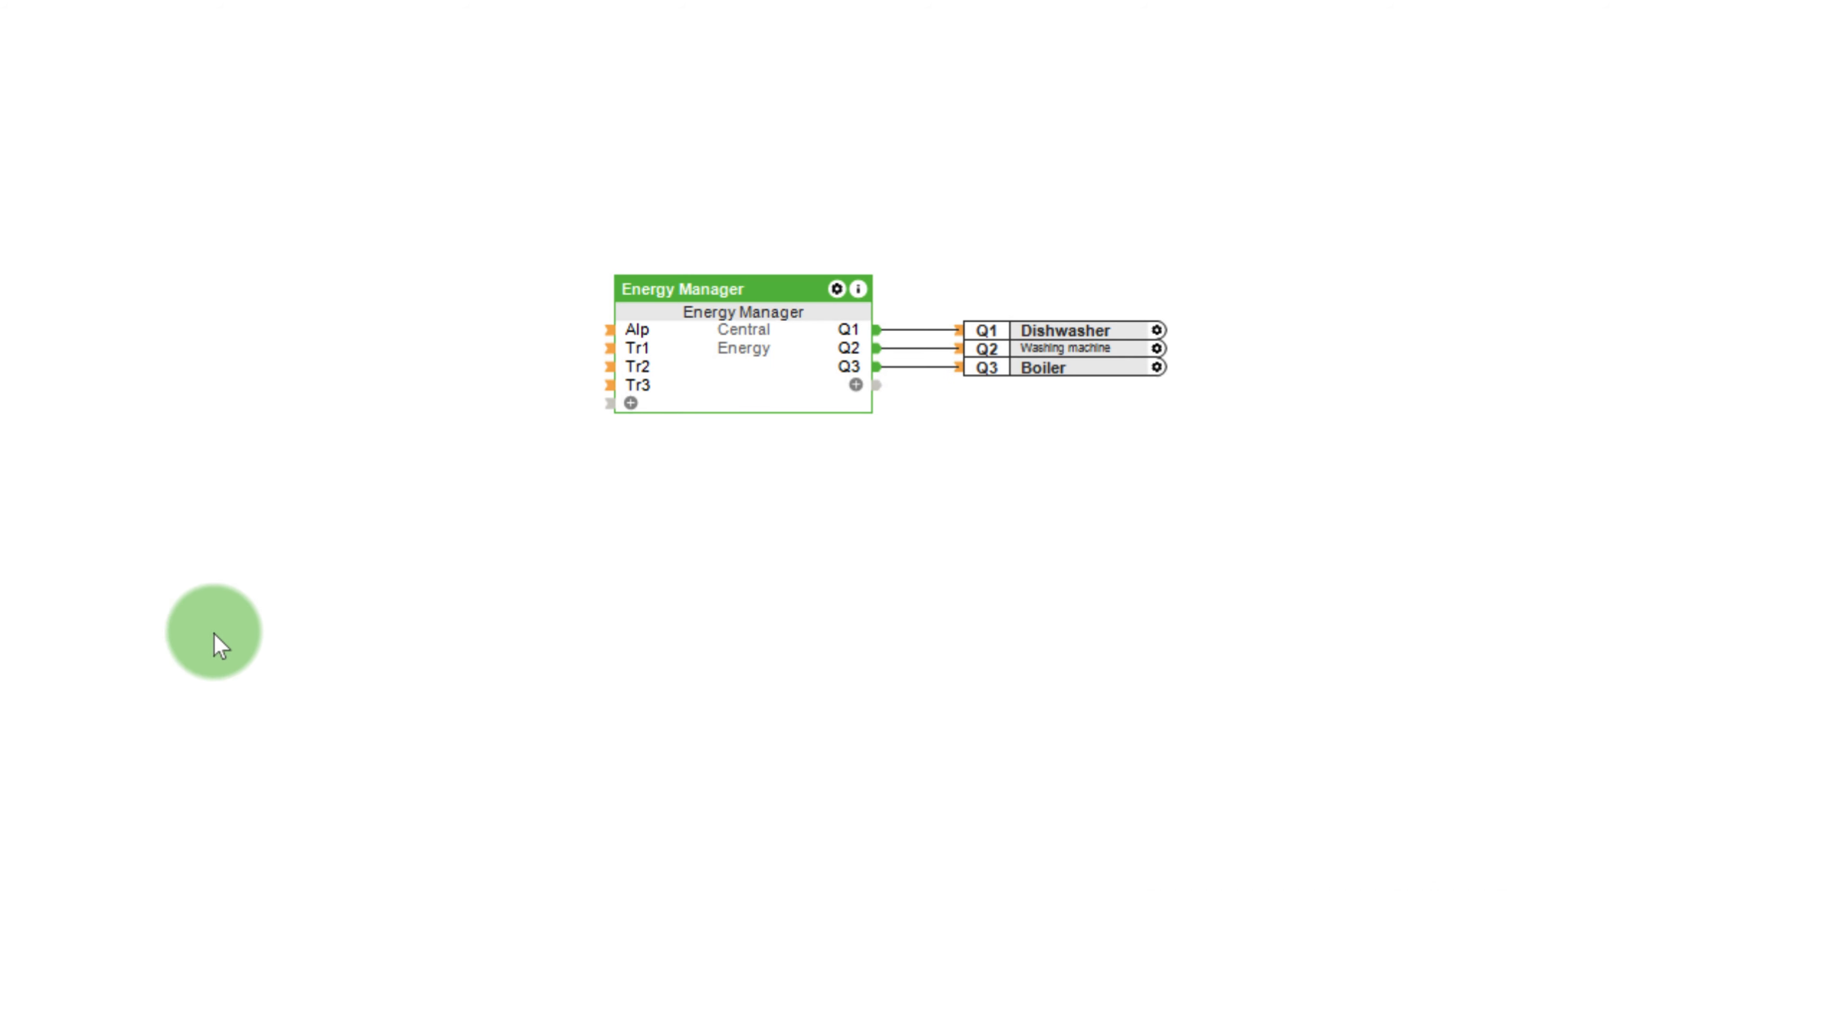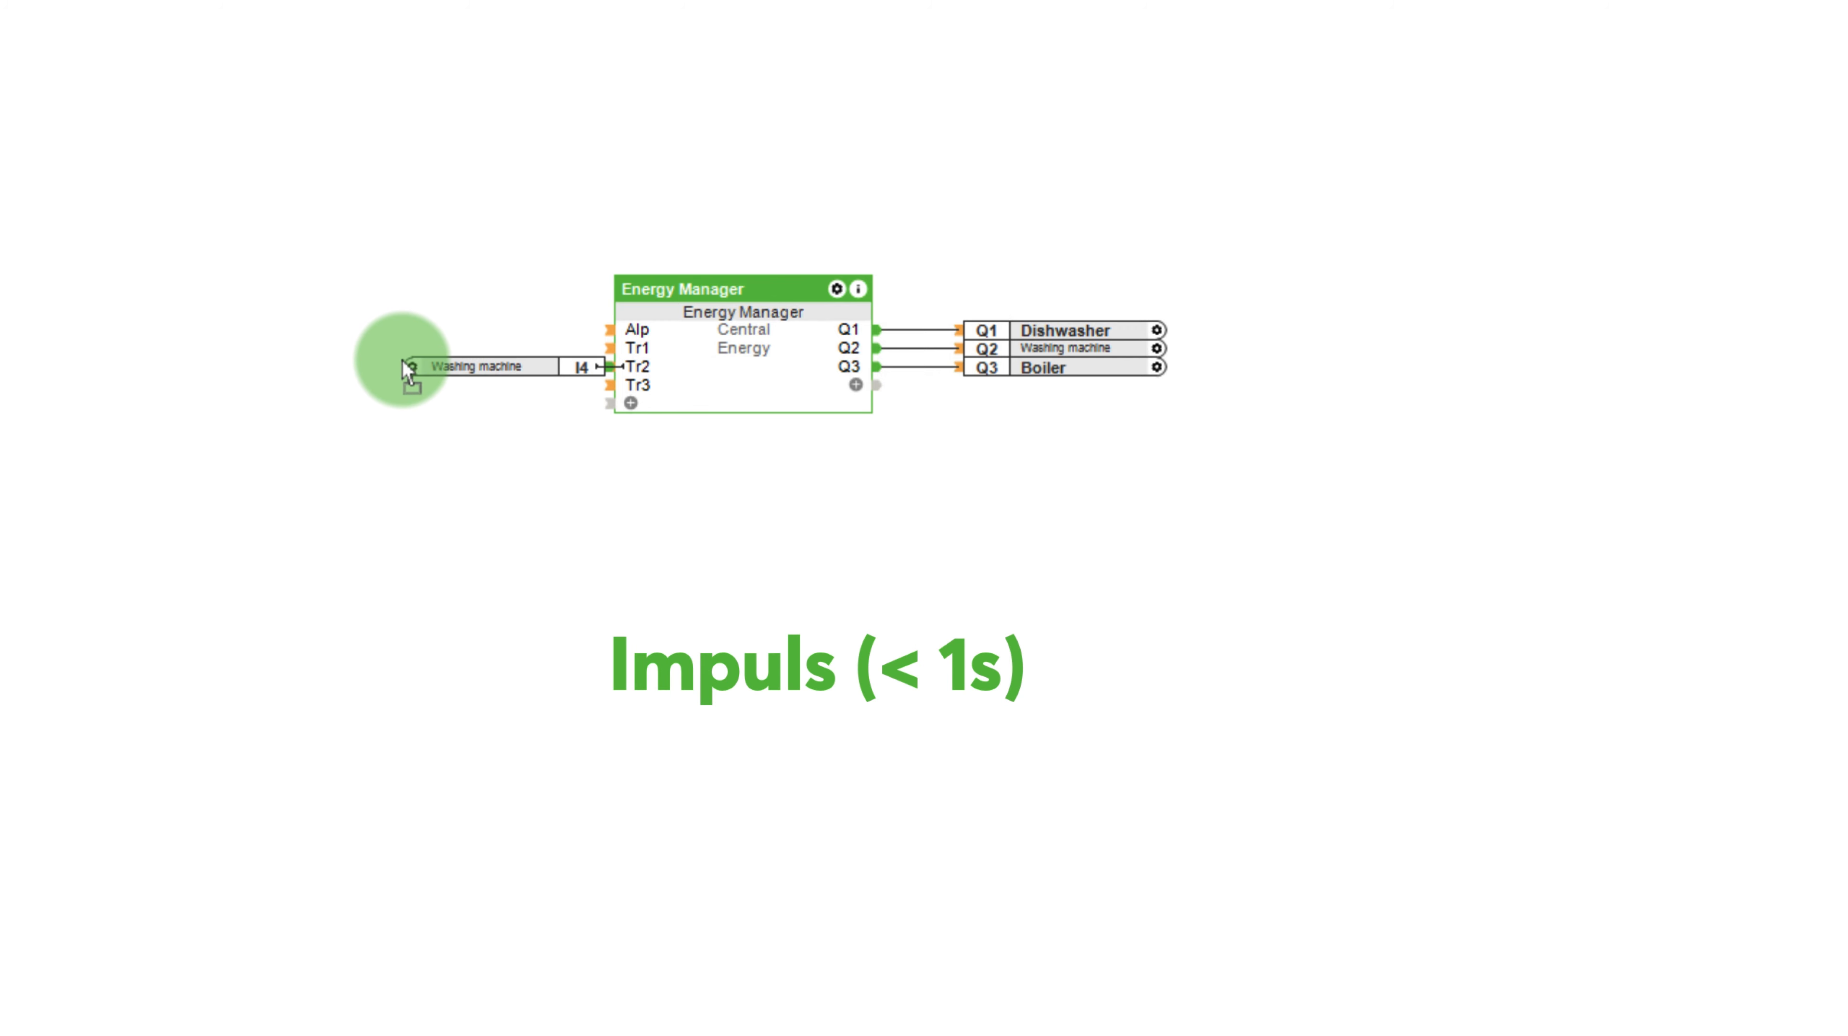If these inputs are triggered with a short pulse of less than one second, the input remains active until the minimum runtime per day is reached. If an activation period is configured for a device, the corresponding trigger input must be confirmed before it can be automatically turned on later.